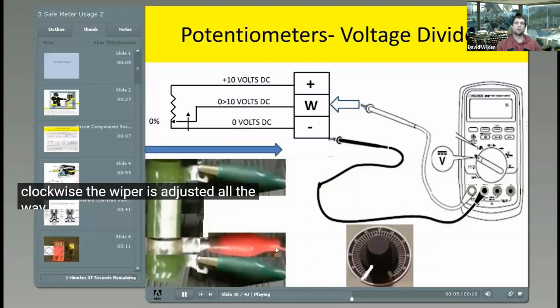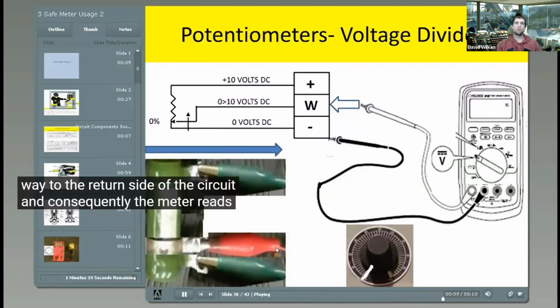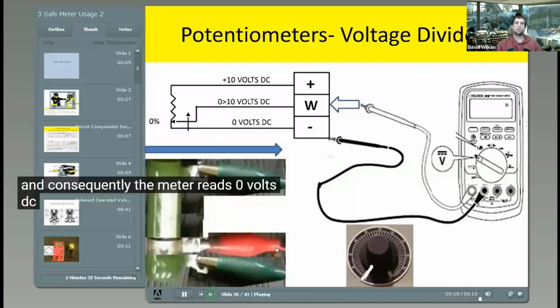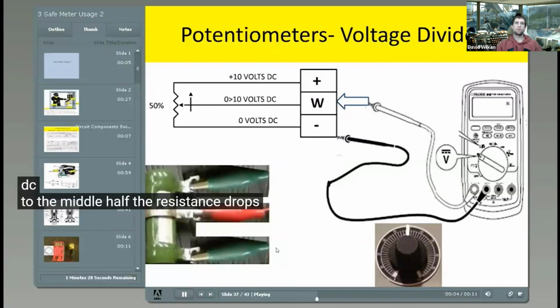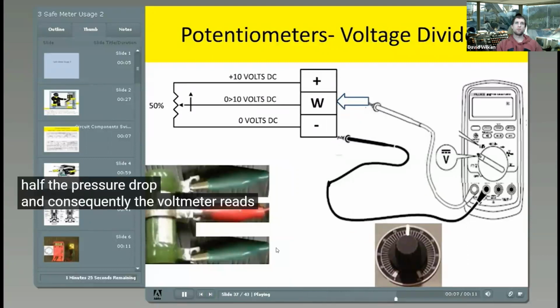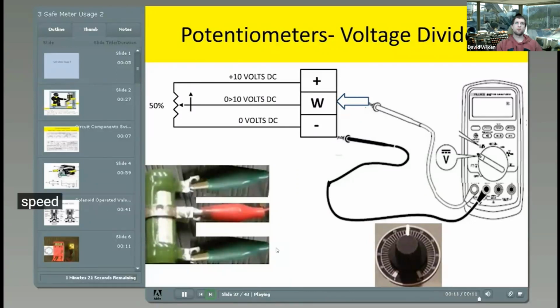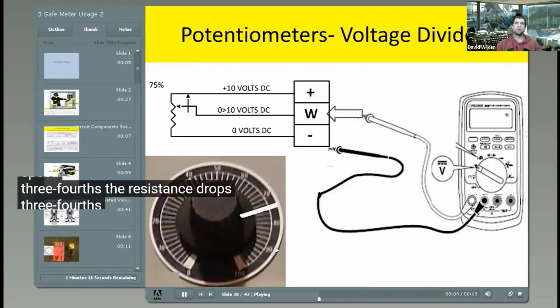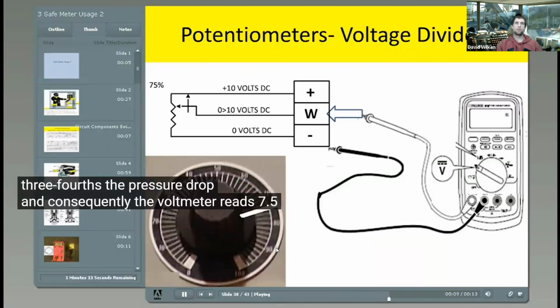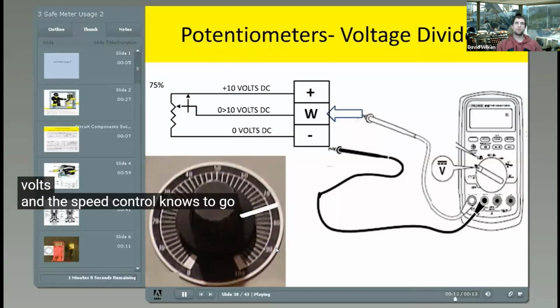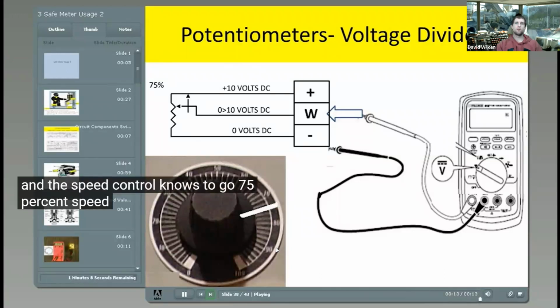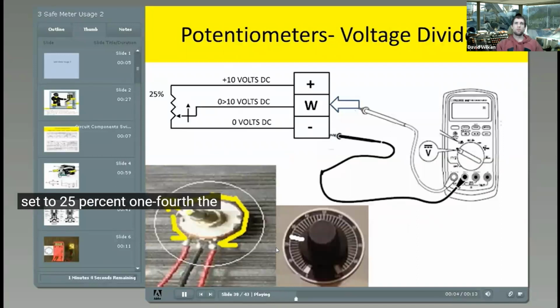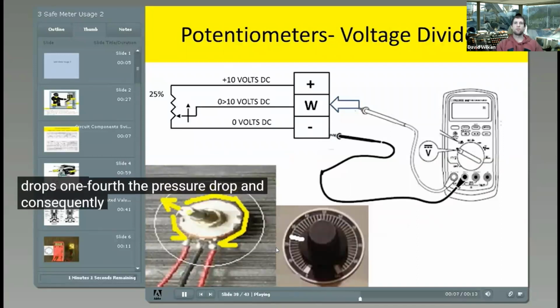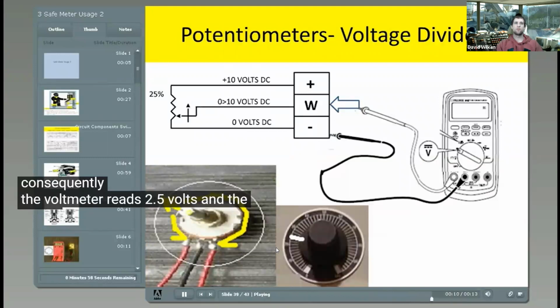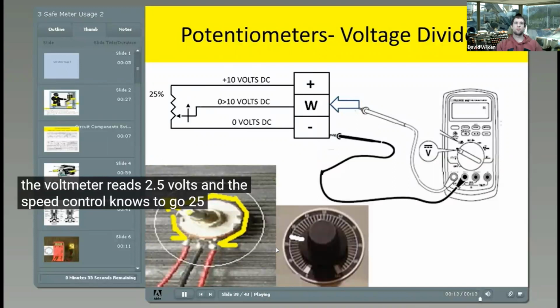Clockwise, the wiper is adjusted all the way to the return side of the circuit, and consequently, the meter reads 0 volts DC. To the middle, half the resistance drops half the pressure drop, and consequently, the voltmeter reads 5 volts, and the speed control knows to go half speed. 3/4 the resistance drops 3/4 the pressure drop, and consequently, the voltmeter reads 7.5 volts, and the speed control knows to go 75% speed. Set to 25%. 1/4 the resistance drops 1/4 the pressure drop, and consequently, the voltmeter reads 2.5 volts, and the speed control knows to go 25% speed.